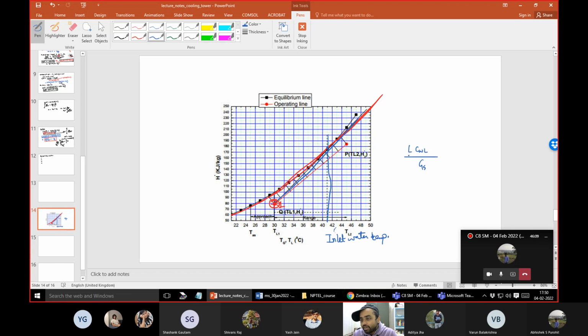So either the liquid flow rate or the gas flow rate will be provided to you. It is most likely the liquid flow rate that will be mentioned to you, because that defines the circulating water rate and the cooling tower capacities also, right? So the liquid water rate is generally provided, and that is decided in the process engineering, right? So you need to find out from this slope what the gas flow rate is for the minimum condition. At the minimum condition, the tower height is infinite, because at the minimum condition there will be a point where the exit conditions of the air and water would be in equilibrium, and to achieve that condition you need an infinite tower, right?